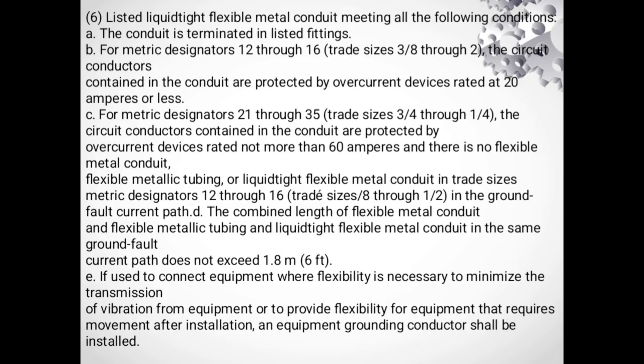flexible metallic tubing or liquidtight flexible metal conduit in trade size metric 12 through 16, trade sizes 3/8 through 1/2, in the ground fault current path. The combined length of the flexible metal conduit and the flexible metallic tubing and the liquidtight flexible metal conduit in the same ground fault current path does not exceed 1.8 meters, 6 feet. If used to connect where flexibility is necessary to minimize the transmission of vibration from equipment or to provide flexibility for equipment that requires movement after installation, an equipment grounding conductor shall be installed. For all circuits, a ground is needed because you can get better performance and less risk for the user and the things around it.